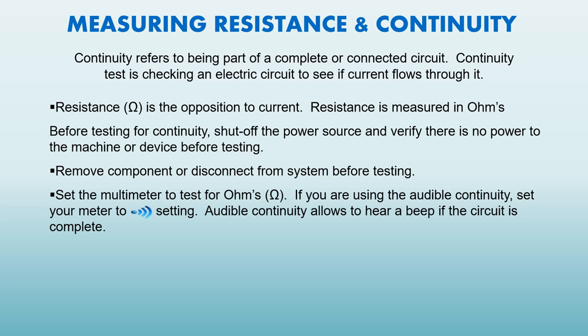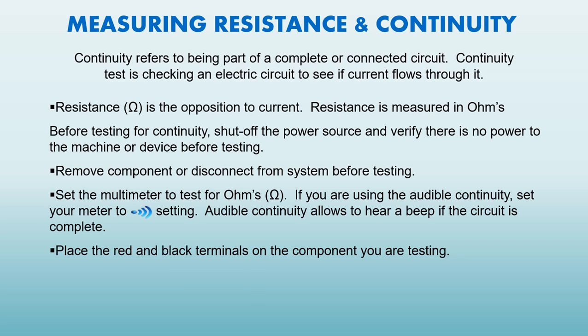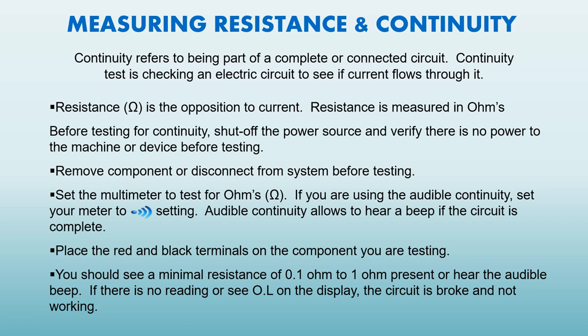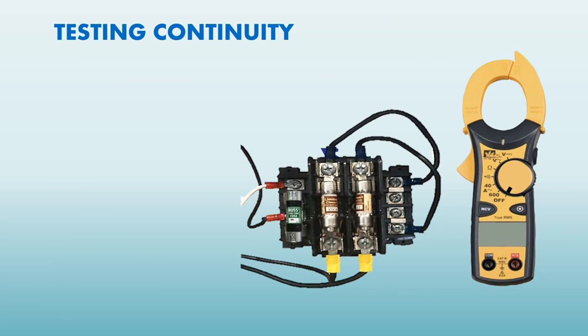Before testing for continuity, shut the power off to the source and verify there is no power to the machine or device before testing. Remove component or disconnect from the system before testing. Set the multimeter to test for ohms, or if using audible continuity, set your meter to audible continuity setting. Audible continuity allows you to hear a beep if the circuit is complete. Place the red and black terminals on the component you are testing. You should see a minimum resistance of 0.1 ohms to 1 ohm present or hear the audible beep. If there is no reading or you see an OL on the display, the circuit is broken and not working.